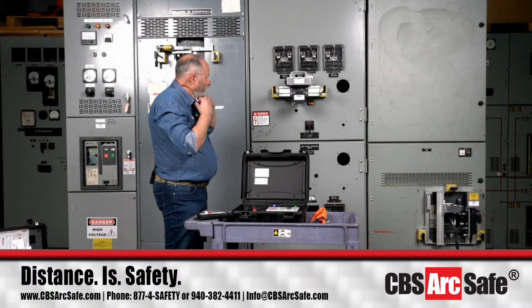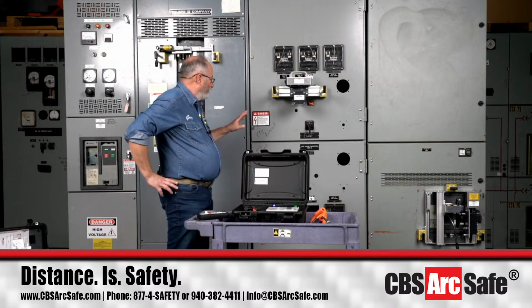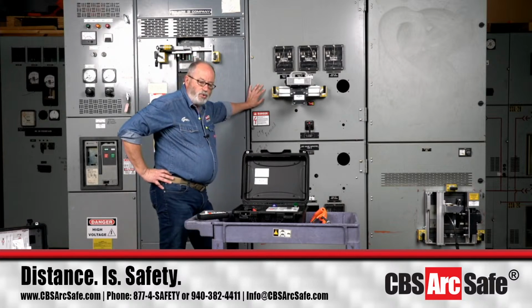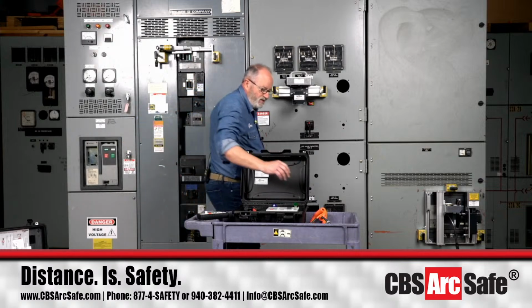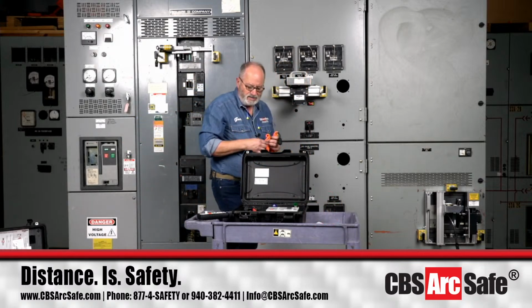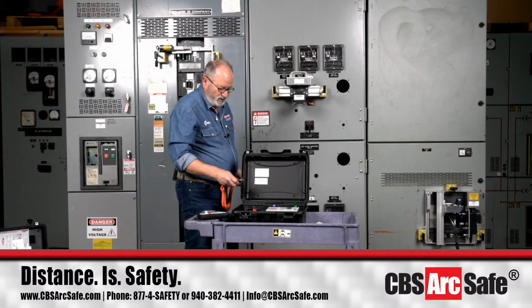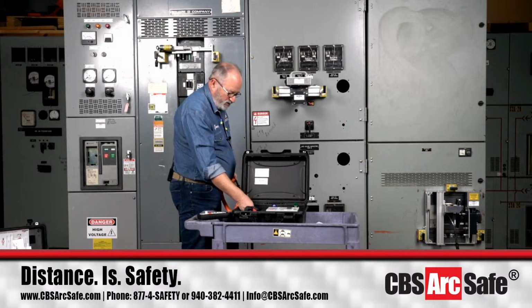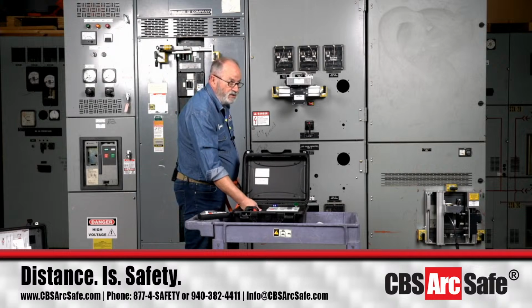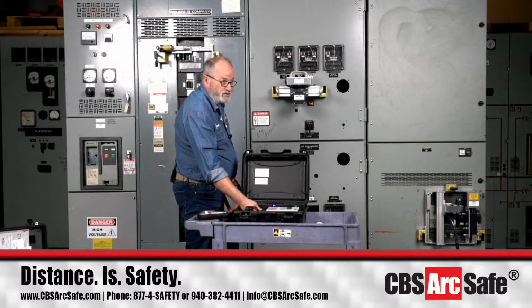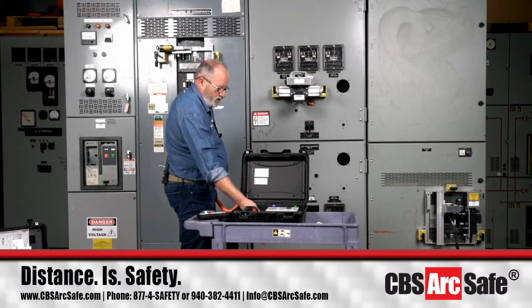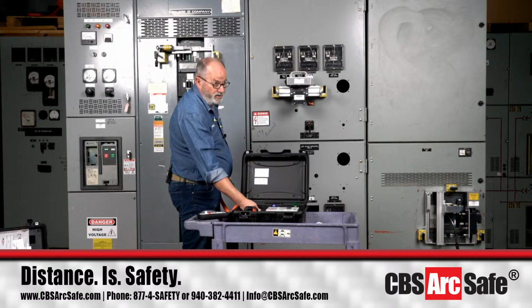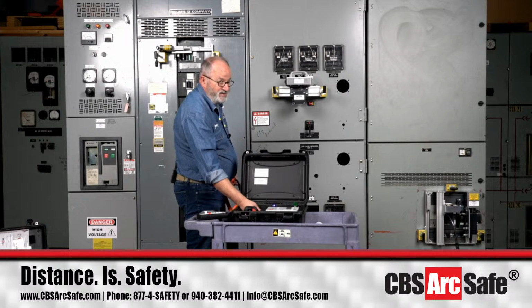Now, the VR breakers you'll normally see are usually a 1200 amp or a 2000 amp, and that's what you're going to see. Most of what we see in data centers today are the insulated case. So you're going to see the Magnum series, the Masterpact series, you may see the Siemens 3WL series, and you might see Emax breakers, second generation now from ABB, or the GE EntelliGuard G breakers. Okay, so those are what are going into the data centers that we're seeing today.